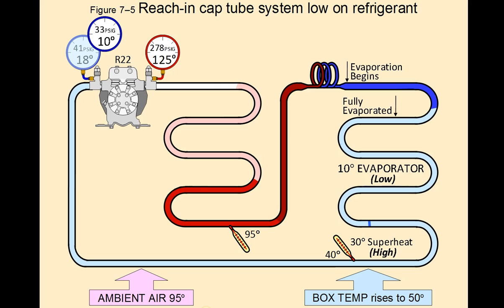On the high side also, let's take a look at this. The system is undercharged and evaporation begins normally at the beginning part of the evaporator coil. But because the system is undercharged, at this point all of the refrigerant has evaporated and has fully changed state into vapor. Through the entire remaining part of the evaporator coil, there is no significant cooling happening because there is no changing of state.